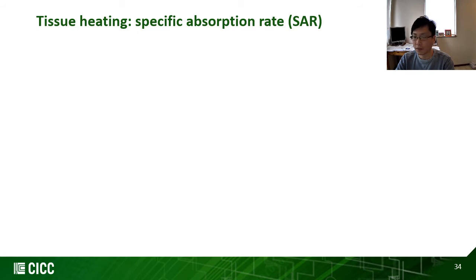In the next two slides, I would like to touch a bit on the topic of tissue heating. When we propagate a signal inside the tissue, there is a potential heating possibility. The regulations specify the specific absorption rate, with a unit of watt per kilogram, in order to quantify potential tissue heating. They also indicate that a smaller implant has higher requirements to meet the SAR regulation. Here I would like to discuss two types of SAR regulation, the electrical version and the acoustic version.